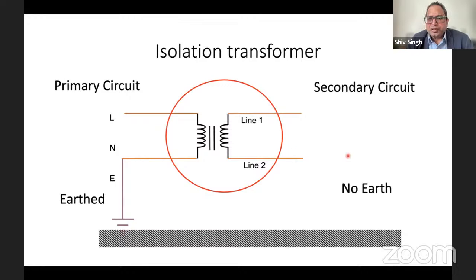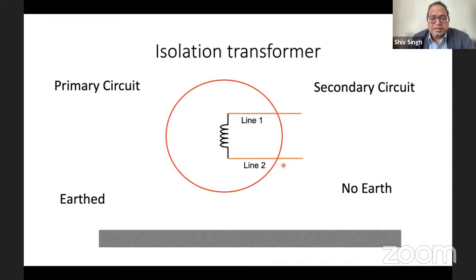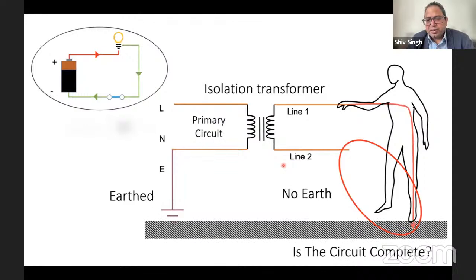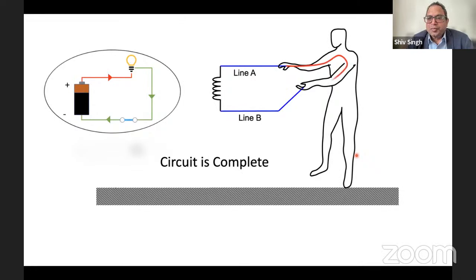You can connect the equipment here, and the bulb will glow. And there's no earth, so we have freed it from there. We can forget the primary circuit. We have the secondary circuit, where we have line one and line two, and there's no earth at all. Now let's consider the same thing. The patient is still standing on the earth. They touch line one, but no current flows through, because the circuit cannot be completed through the earth. Since line two is not connected to the earth, it can't be completed. Unless there is also earthing of line two, you cannot complete a circuit. Or you would have to be stupid enough to hold both line one and line two to complete a circuit. That you're not going to do, are you?